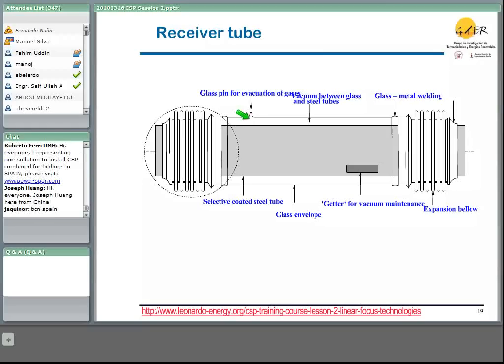In this diagram, we can also see some other elements, like these getters for vacuum maintenance, because during the operation of parabolic trough plants, especially those which operate with thermal oil, as we will say immediately, there are some leaks of hydrogen generated by the decomposition of the thermal oil into the space between both tubes.